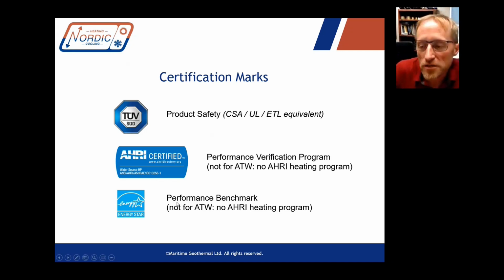Quite often, you'll see requirements, especially for grant programs, that something like a heat pump carry the AHRI certified mark, or the Energy Star, which is a benchmark. It's basically the same group of equipment. For air-to-water heat pumps, as I mentioned before, there's no AHRI program for air-to-water heat pumps in heating mode. So you won't find these on ATWs, and it's not because the ATW doesn't qualify for AHRI or that we haven't bothered to certify it. It's that there's no program existing. So I'm sure that'll be changing, and when it does, we'll have that mark on there.